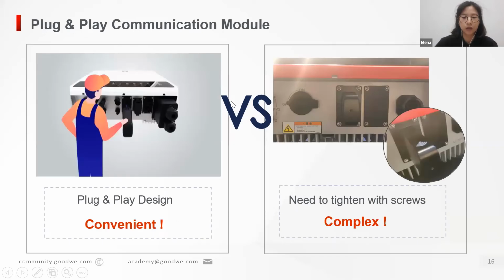Wireless communication is necessary for the local commissioning of an inverter without a display screen. It is also essential for remote controlling and monitoring, especially for the residential solution. Almost all inverters will be equipped with wireless communication modules. So we provide plug-and-play communication modules, which are more convenient for installation, such as Wi-Fi, Bluetooth, and 4G modules, according to the different requirements. The installer only needs to simply connect the module to the inverter with the USB port, and they can configure it with our app.